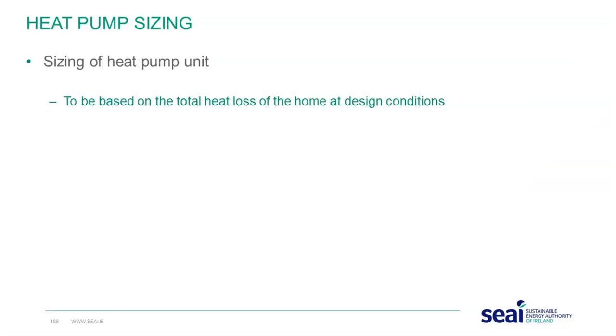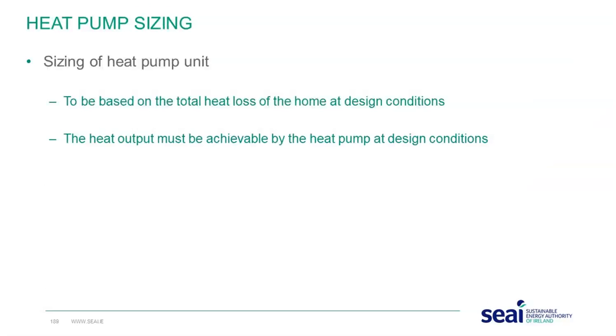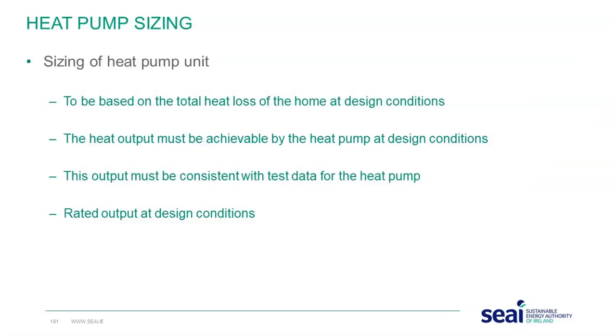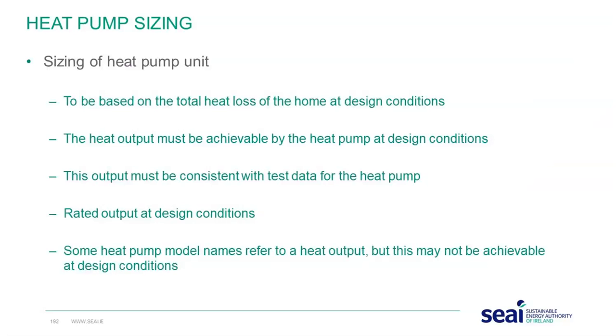So when we go to size the heat pump, what do we need to consider? It has to be based on the total heat loss of the home at design conditions. The heat output must be achievable by the heat pump at design conditions. The output must be consistent with the test data for the heat pump. So just make sure you don't mix up models, etc. It must be rated output at design conditions. Some heat pump models will refer to a heat output, but just be careful because this may not be at the same design conditions.